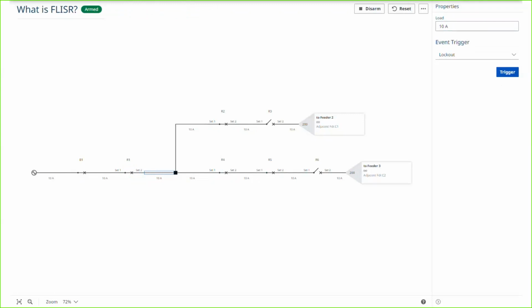If feeder 3 had like a hotline tag or a supervisory cutout applied, it wouldn't have told us it could give us 10 amps. It would have told us it can give us 0 amps. Right? There's work happening over there. We don't touch feeder 3 when work is happening. So you would see a similar behavior, except R6 wouldn't have closed at all.